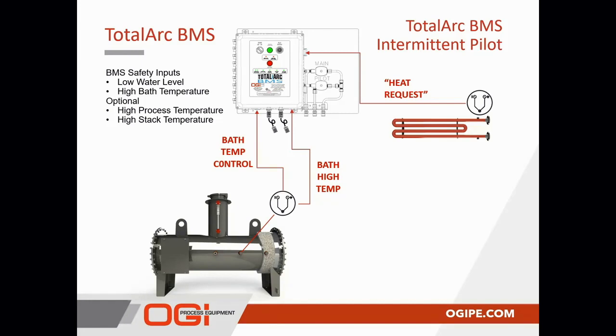In the intermittent pilot mode, as it was for the pneumatic control configuration, when a call for heat signal is received, the pilot will light and be proven, and then the main burner will be lit. And this is all based on the call for heat condition versus just a standing pilot and the main burner coming on with a call for heat. Note that the call for heat signal will vary depending on whether the heater includes both the bath and the process temperature controllers for this condition.